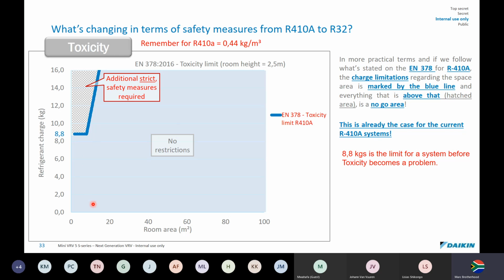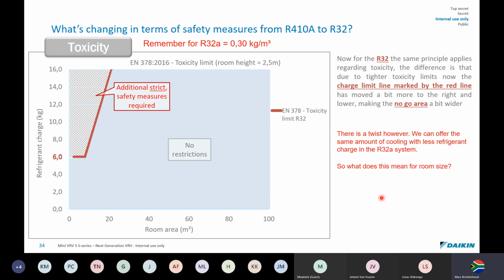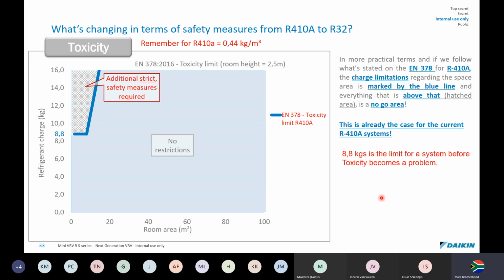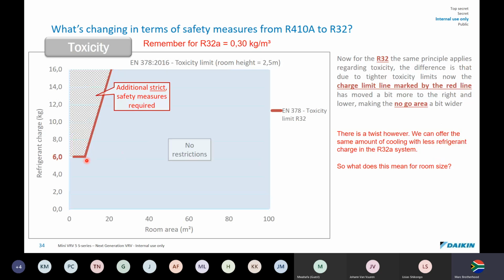So if we draw a line down here and the room was, say, 15 square meters, this is where we could apply. If there was 10 kilograms or 12 kilograms of gas in the system, because it's a long pipe run, you'd see we'd fall into this cross hatching, and it wouldn't be advisable to use a system on a room this small with that much gas. So the limit here is about 16 kilograms and about a 20 square meter room. But like I said, if you have a small room, 10 square meters, the most gas that you can have in the system is 8.8 kilograms. You can't have more than that in case of a gas leak, as then the room becomes too toxic. That is 8.8 kilograms for 410. For R32, we drop that to only 6 kilograms.